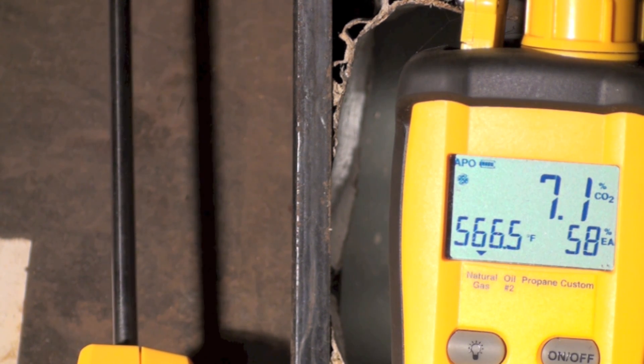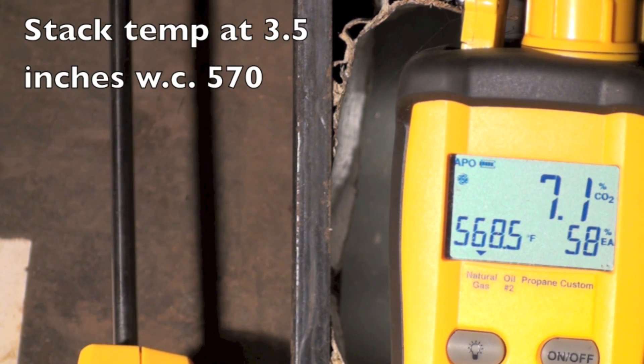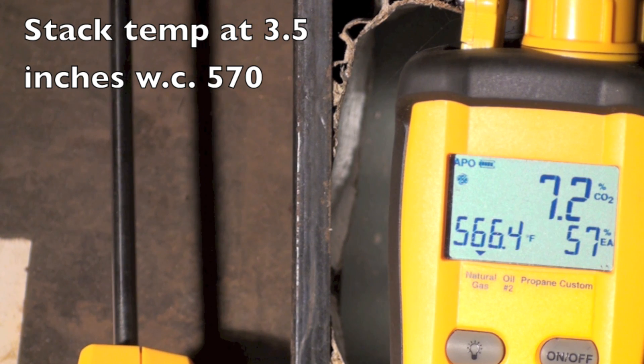Stack temperature - it can go down a heck of a lot, didn't it? Excess air went way up because I'm moving less gas to there, so there's a lot more excess air. Let's see what the efficiency is.